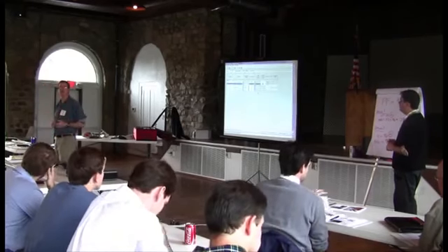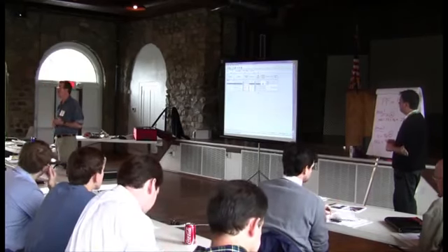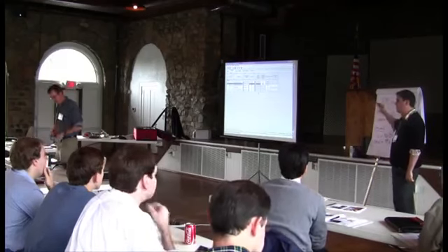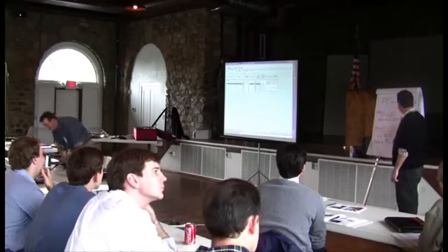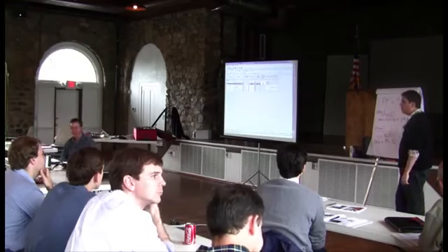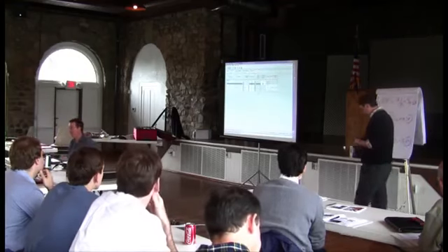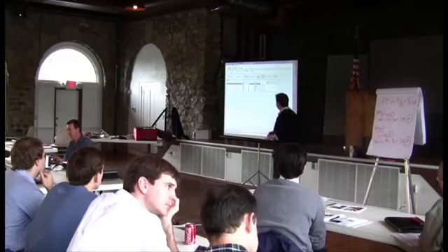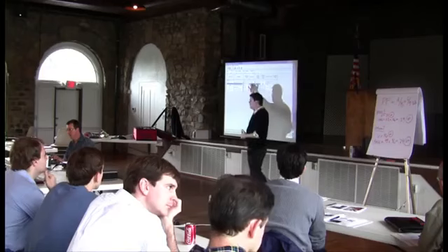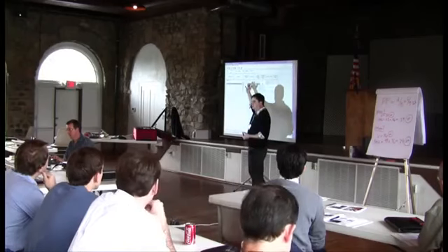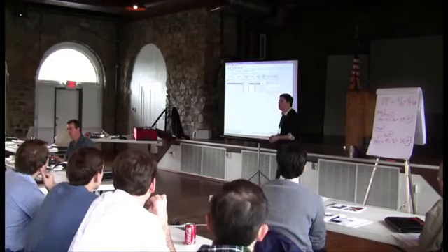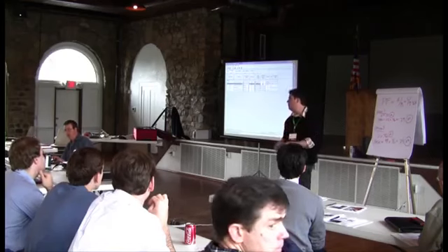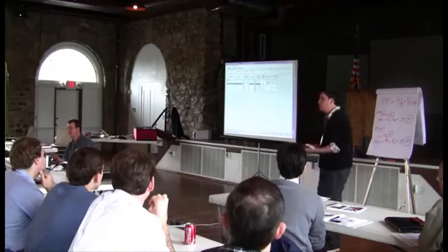That's, in essence, what this software allows you to do. So remember, Mike is using the same example, the same glass as option 1, that actually did not work prescriptively, but we made it work here. Probably some of that is, if you look at this from a square footage percentage, we've got more roof area and less wall area. Maybe if that was a 5-story building, with 3,500 square feet of roof area but a lot more skin area, that might not work. But that's correct.